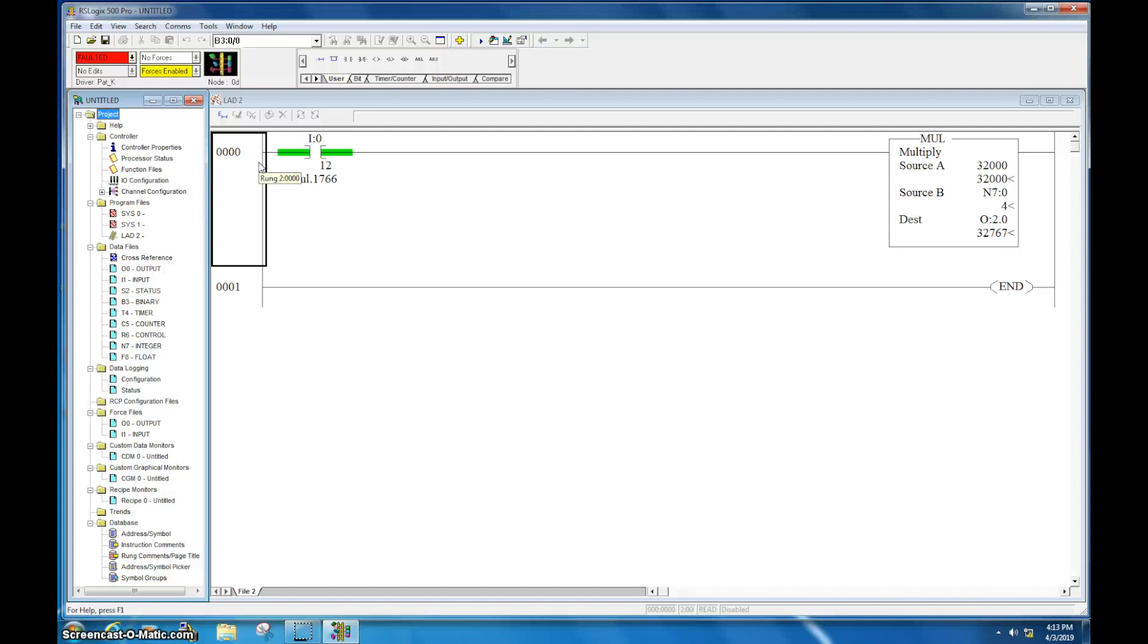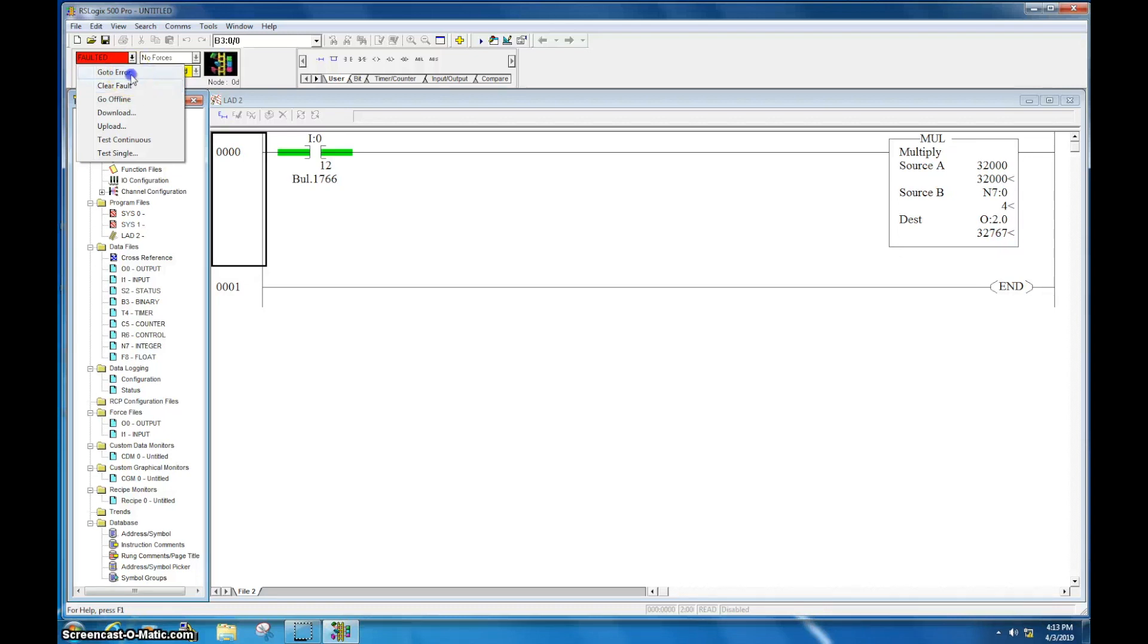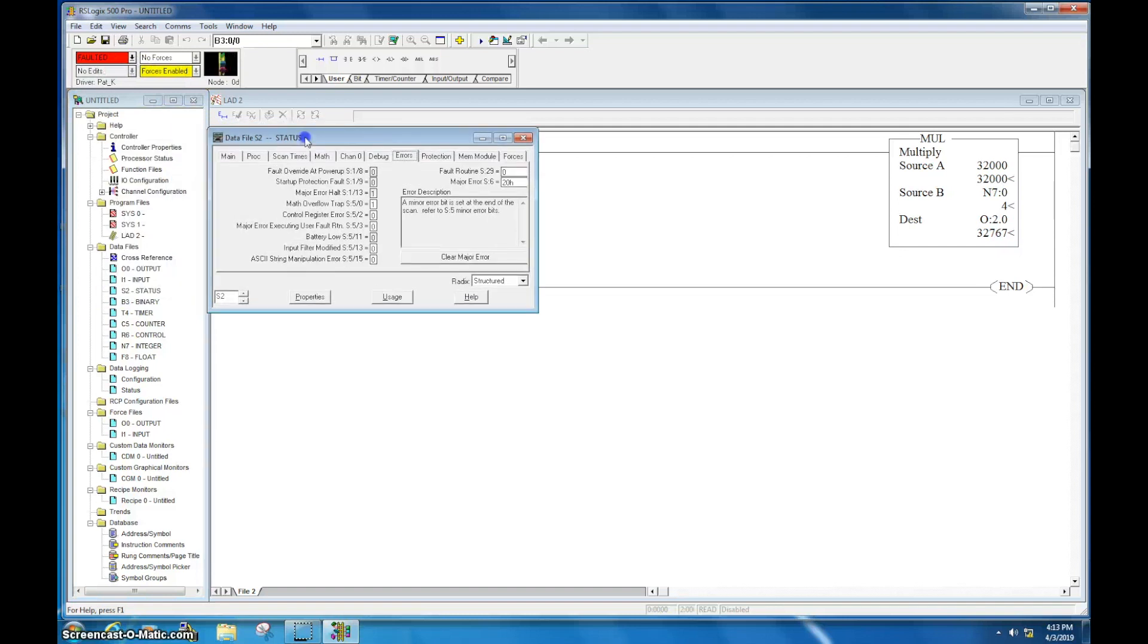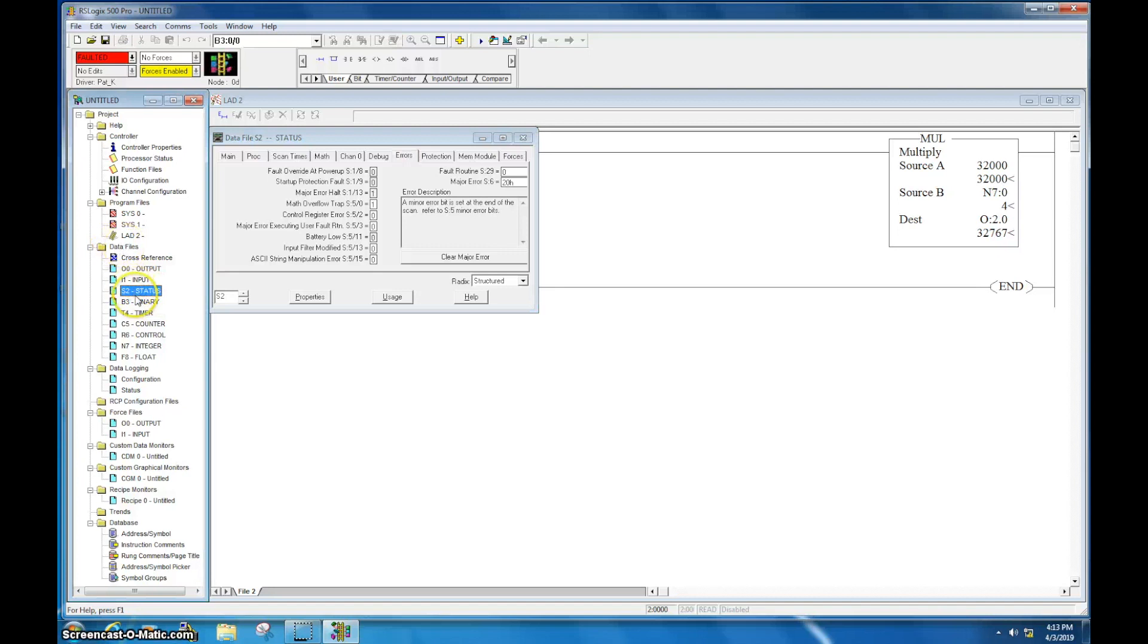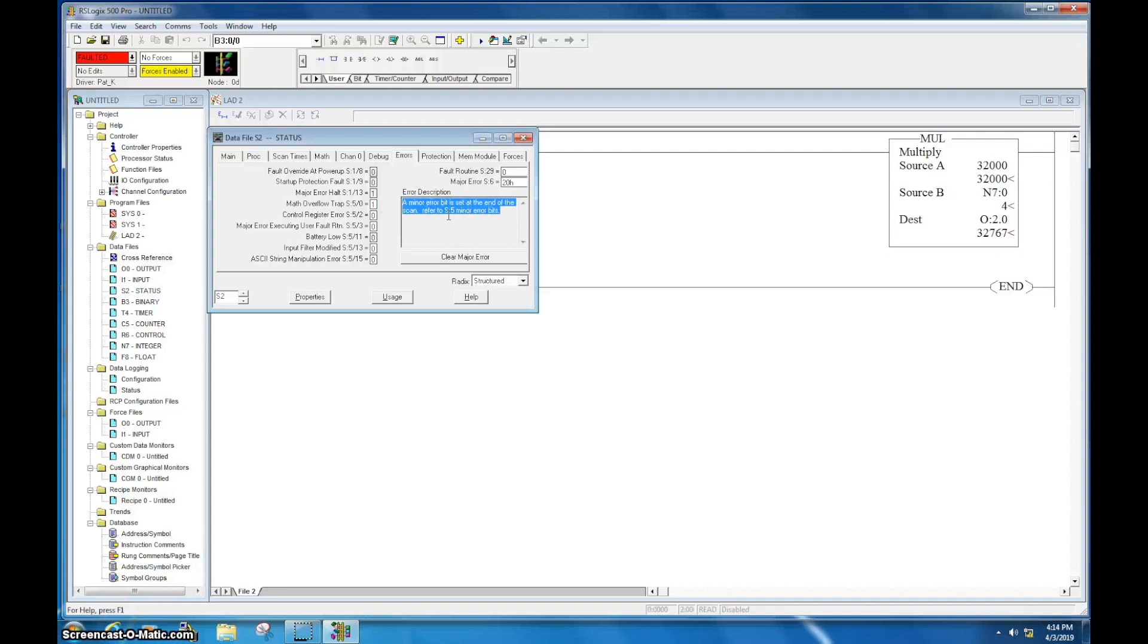So now you can see here on the screen a very simple program that I created to create a fault. But I still don't, I may or may not know what the fault is. It may not be obvious right here. So right now it says faulted. So I'm going to click here and I'm going to go to, go to error. I could clear the fault and sometimes that will take care of the problem, but we're going to go ahead and go, go to error. This will bring up your S2 data table file, which is actually located right here in your data table files. In here you see the tab that says errors. This will actually sometimes, most of the time, give you the error description. So, a minor error bit is set at the end of the scan. Refer to S5 minor error bit.